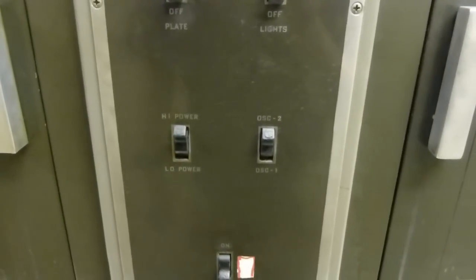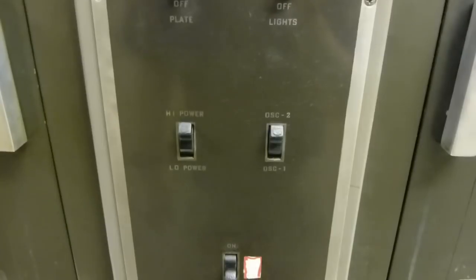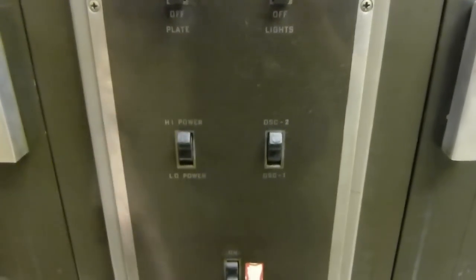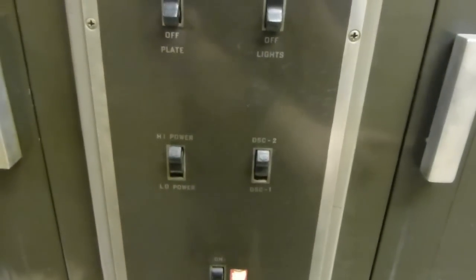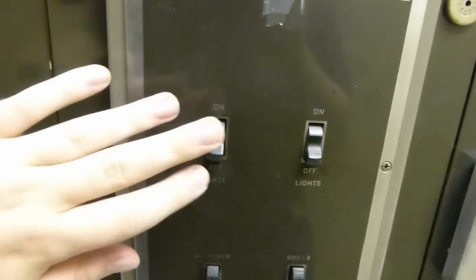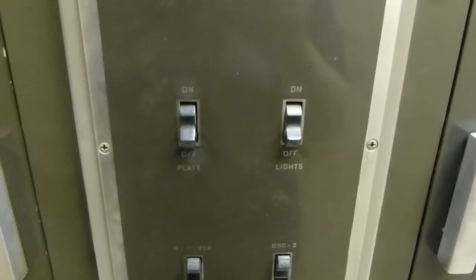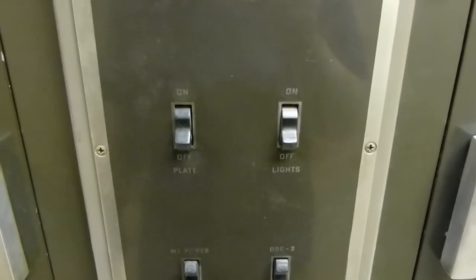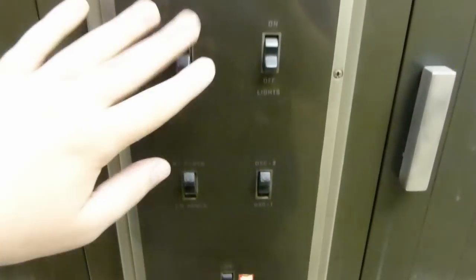If we were a station that needed to drop power at night rather than just go to a directional transmission pattern, this would serve to drop the power from 5 kilowatts down to 1 kilowatt. Over here is a switch that switches between the two oscillators in the other cabinet. This just turns on the lights I mentioned earlier. And then this switch is the real fun one — this turns on the plate supplies. It energizes a series of contactors that will turn on the low- and high-voltage plate supplies when the time comes, because they can't just be turned on immediately.